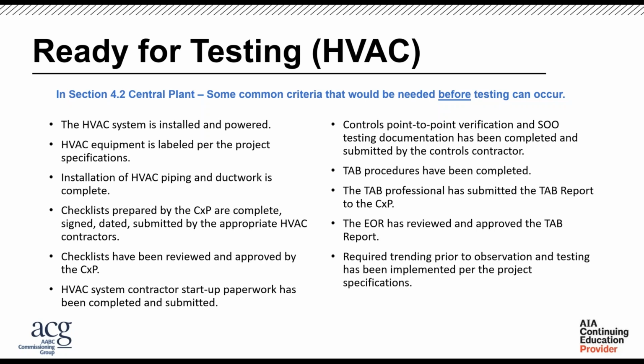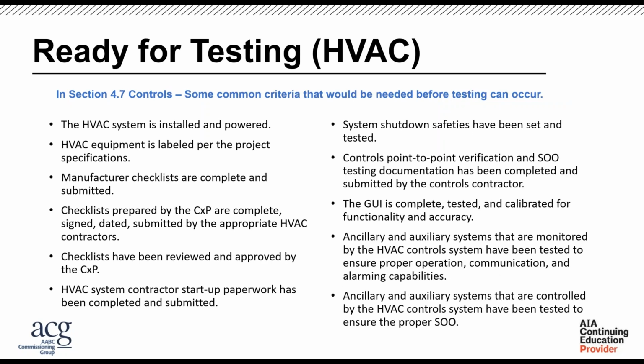programmed in the system. And we've run through this many a time where the controls might come a little bit later in the process. So these are things for pretty much every piece of equipment. You need to make sure that they're ready. And speaking of controls, I can't stress enough the importance of controls nowadays, as controls are on pretty much every phase, almost every piece of equipment that you're going to test mechanically, and of course even electrically.